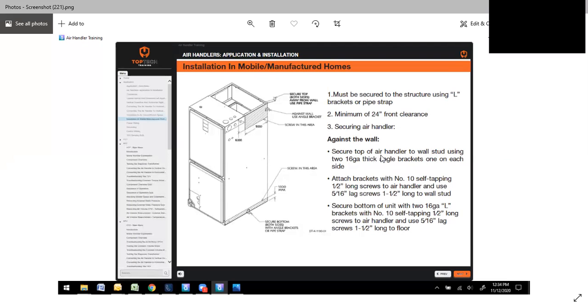Secure the top of the air handler to the wall stud using 2 16-gauge thick angle brackets, 1 on each side. Attach brackets with a number 10 self-tapping half-inch screw to the air handler. Lag screws to the 1.5-inch wall stud. Secure the bottom of the unit with 2 16-gauge L brackets, number 10 self-tapping half-inch screws, and use 5/16 lag screws 1-1/2 inch long to the floor. Since it's a mobile home, it's got to be secured and stable.